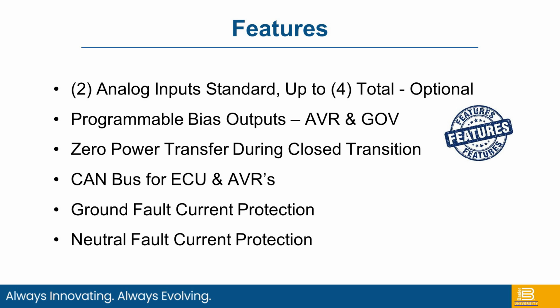Basically, what we utilize is if you're not using analog inputs like a resistive or analog oil temperature or pressure, we can repurpose those, especially when you're using an electronic engine, which most of the engines today that are being manufactured are all Tier 4 Final or Stage 5. Programmable bias outputs for the AVR and the governor.